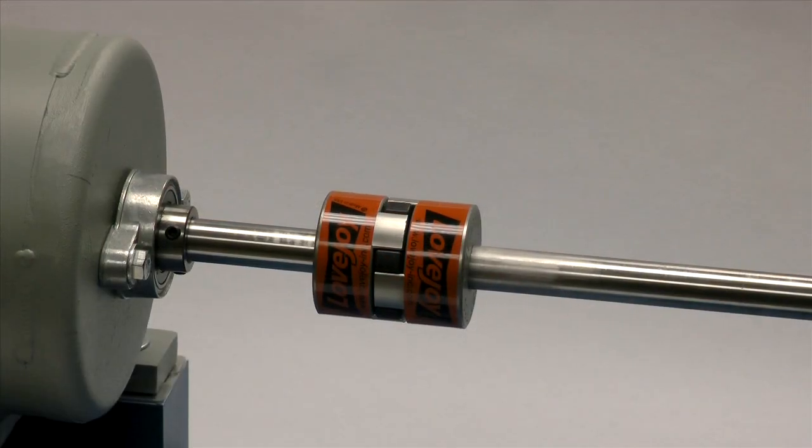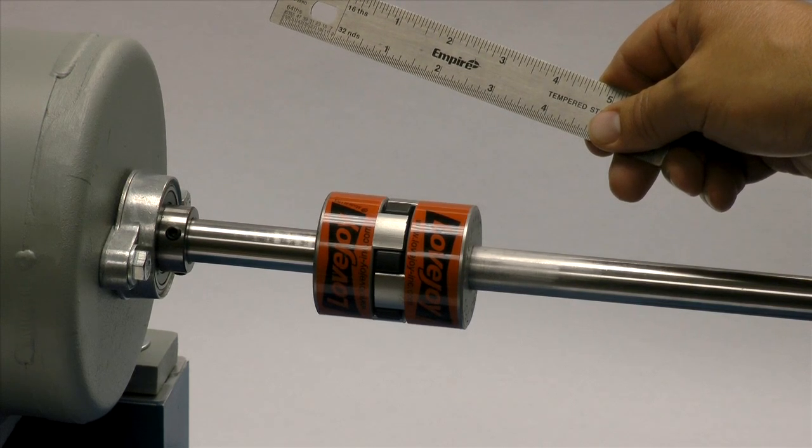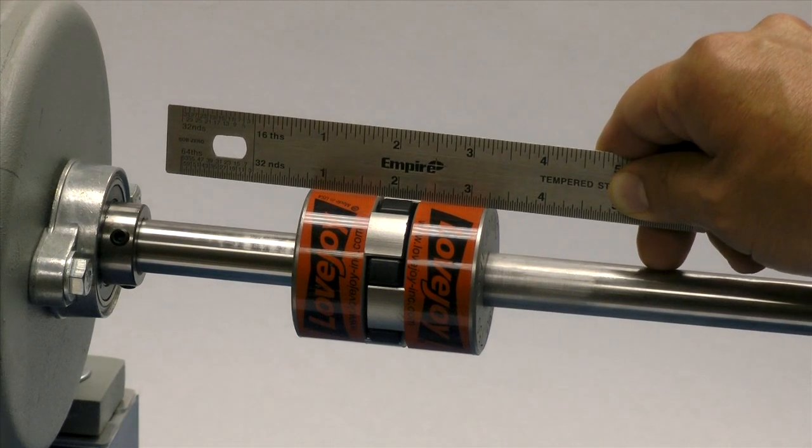Lay a straight edge across the hubs to check the basic alignment. If all sides of the coupling are accessible, check the hubs at four locations: 3 o'clock, 6 o'clock, 9 o'clock, and 12 o'clock without rotating the shafts.